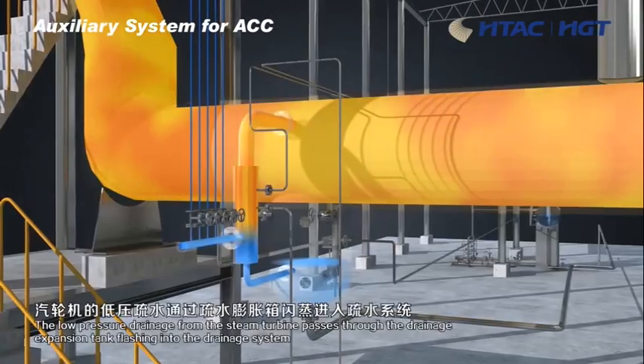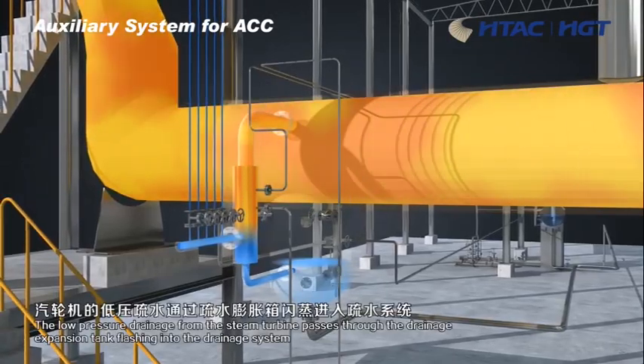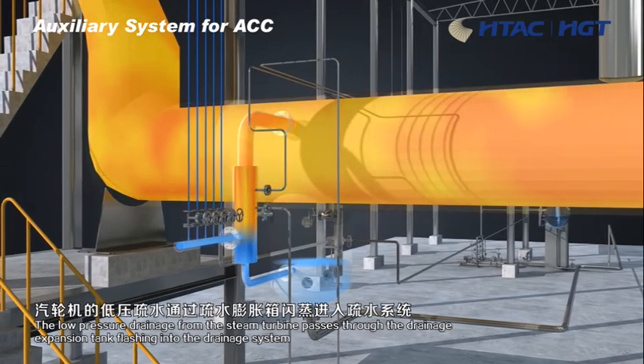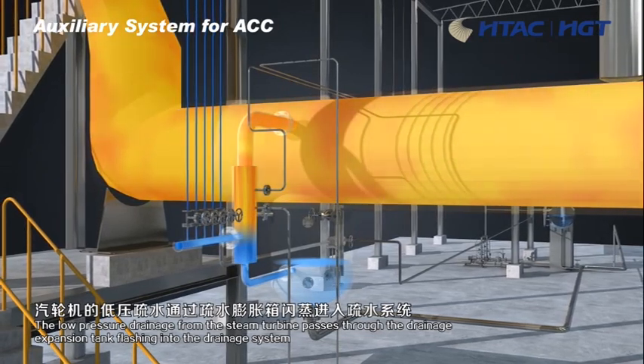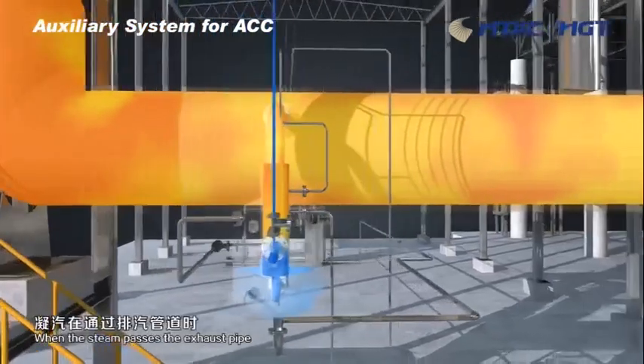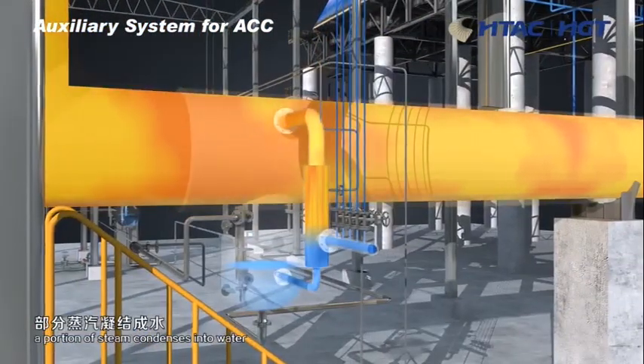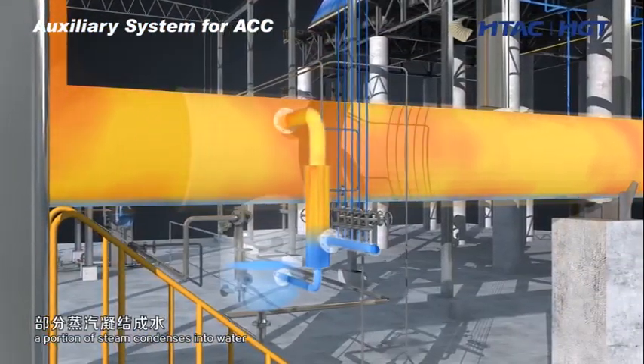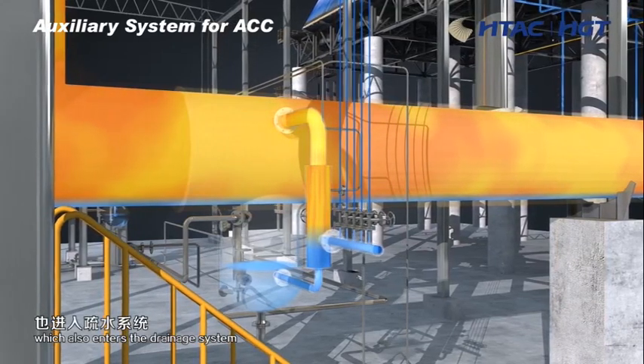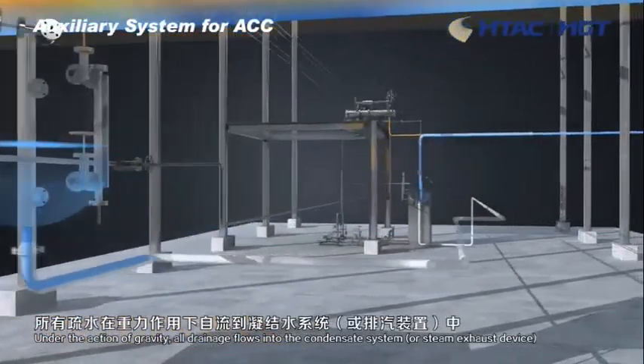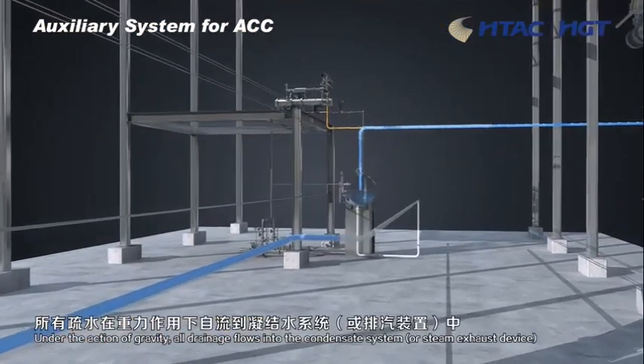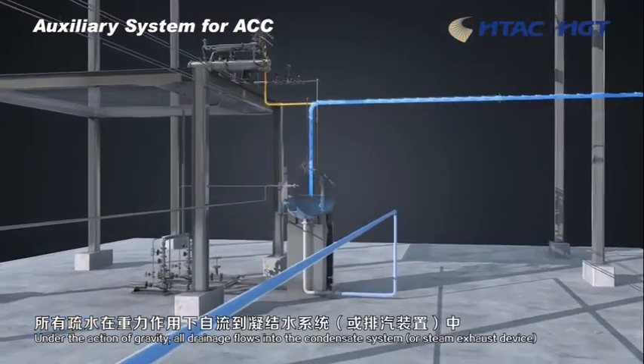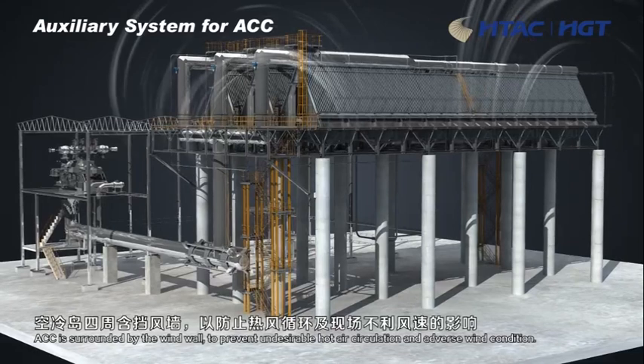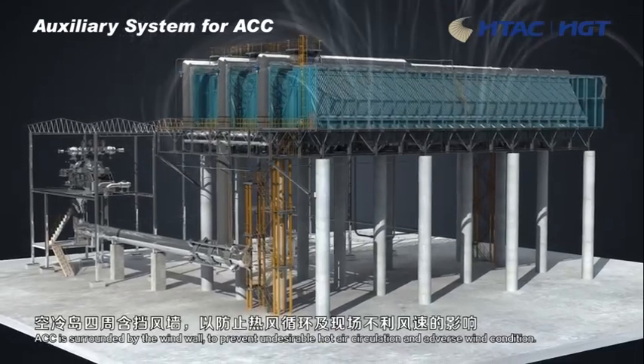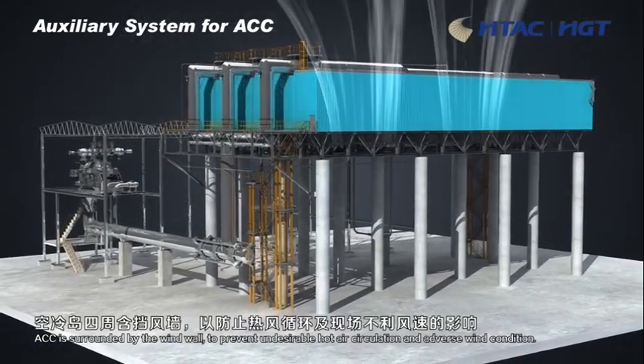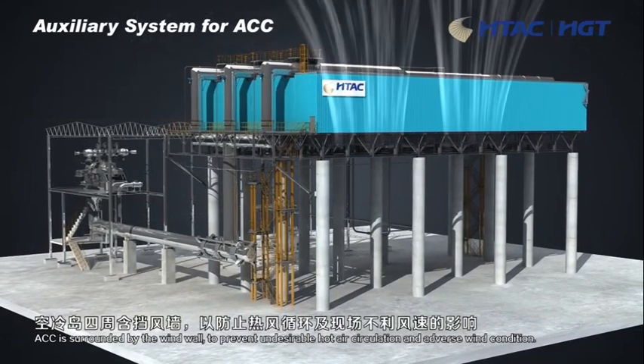The low-pressure drainage from the steam turbine passes through the drainage expansion tank, flashing into the drainage system. When the steam passes the exhaust pipe, a portion of steam condenses into water, which also enters the drainage system. Under the action of gravity, all drainage flows into the condensate system or steam exhaust device. ACC is surrounded by the wind wall to prevent undesirable hot air circulation and adverse wind condition.